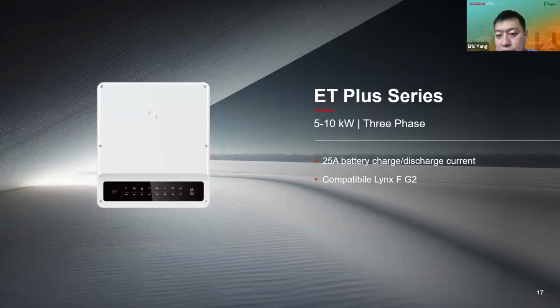And this is the ET Plus series. The power range is from 5 to 10 kilowatts. This is the three-phase hybrid inverter, and it connects to the high voltage battery. So the battery charge and discharge current is only 25 amp, but we think 25 amp is enough for this 5 to 10 kilowatt hybrid inverter. And also it can work with GoodWe Lynx F G2 series.